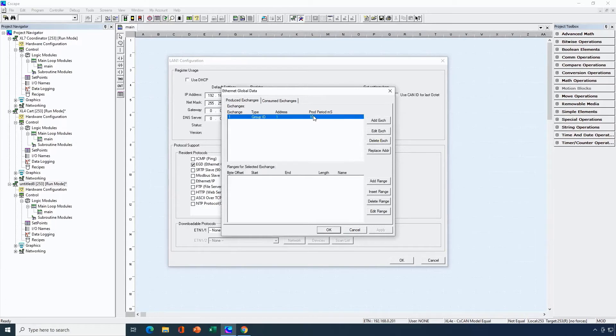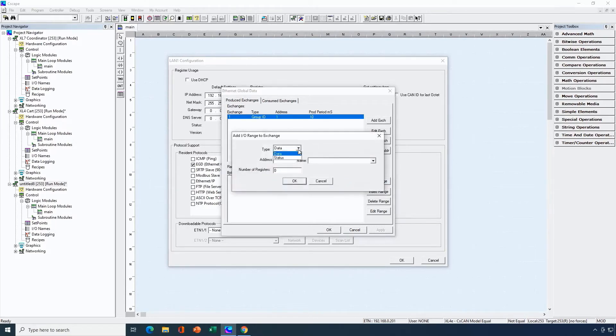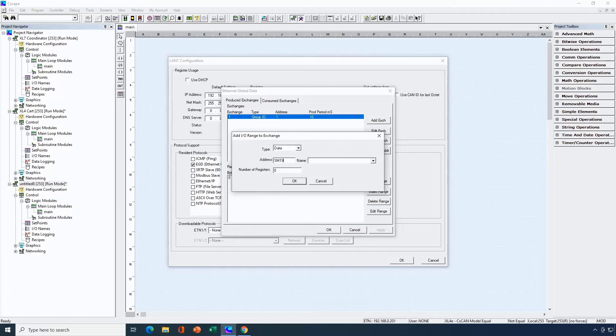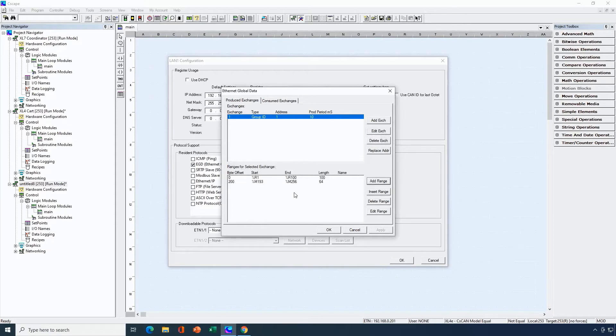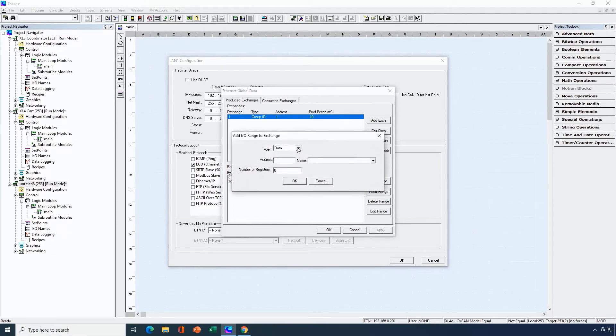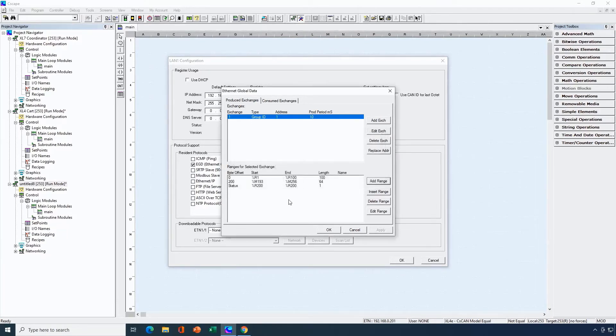I'll make sure the exchange is highlighted and hit add range. Our choices are data and status — we'll look at status later. Then I input the address I want to start at. Let's say we want to start at register 1 and we want 100 registers, so we're putting 100 words in R1 through R100 in the envelope. Next let's say I want some bit type data — we'll start at %M193 and put in 64 bits. This needs to be on a word boundary so I selected M193. Now I'll hit add range again and this time add status. Register 200 is going to be the status register for my produced data. That's the configuration on the produced side complete.